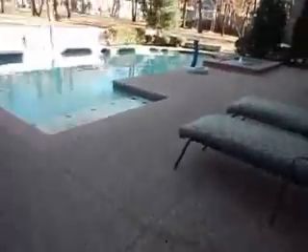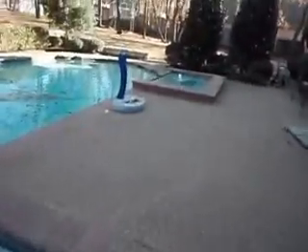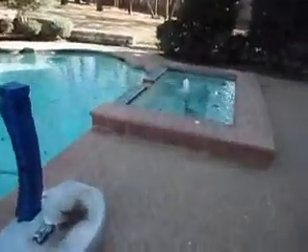This is the blower unit. Oh, it's on. Let's go and see if it works. Hopefully it will, but I wouldn't be surprised if it doesn't. They've got a little plastic tube that takes it back to a micro switch, it's pneumatically operated. That plastic tube deteriorates over time. No, it's not working. So the blower's not working.